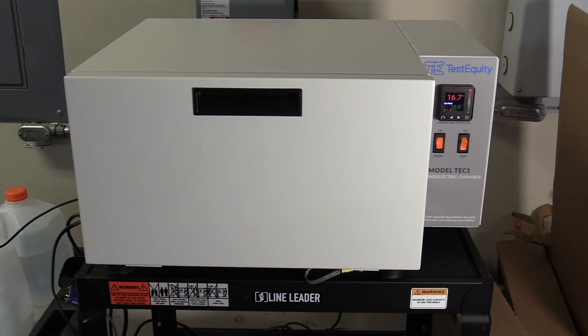It is extremely small in visible light, but with the sensors that I've been working with, it is a little bit more significant in the ultraviolet. To that end, I have decided to perform full thermal calibration for the upcoming UV-Vis Densitometer.